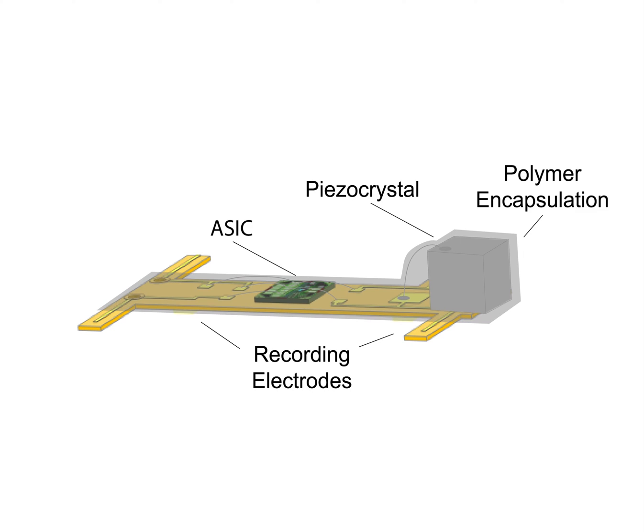The sensor consists of a piezoelectric transducer for harvesting ultrasonic energy, a custom ASIC for communication, and recording electrodes on the back side of the implant. The implants are encapsulated in a medical grade epoxy to provide insulation. Test leads can be used to measure the voltage across the transducer and the signals from the recording electrodes.